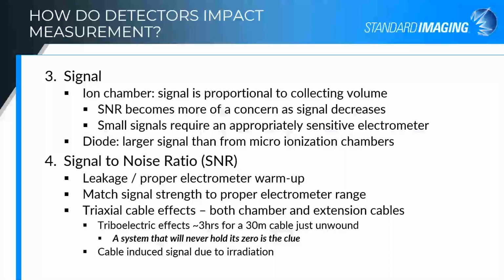Consider your signal to noise ratio. I know I brought that up under the signal bullet up above, but in terms of your signal to noise ratio, you need to be sure that you have proper warm-up for your electrometer. All of those electronic components, the resistance changes slightly, that sort of thing, as they come up to temperature once they're on, once the bias is on. So check your leakage, make sure that your system is stable, make sure you give your electrometer a sufficient warm-up. Match the signal strength that you're measuring with your detector with the appropriate electrometer range.